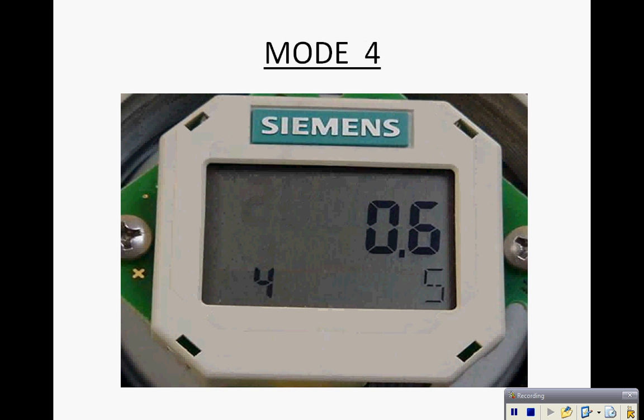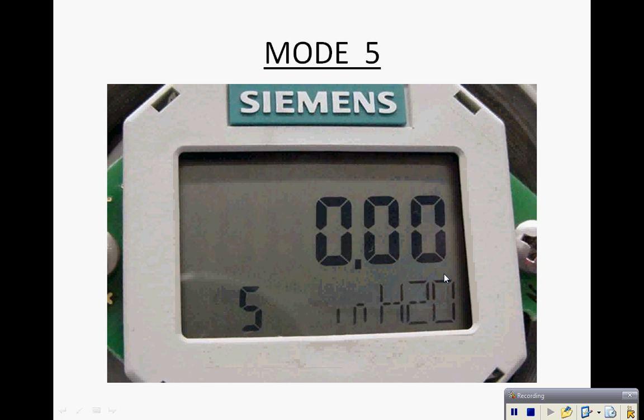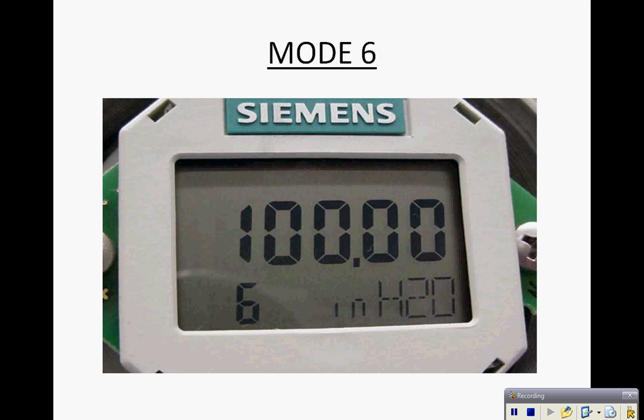Mode 4 is the damping adjustment in seconds. Mode 5 is where we set the zero without a pressure source applied. Mode 6 is where we would set the full scale without a pressure source applied.